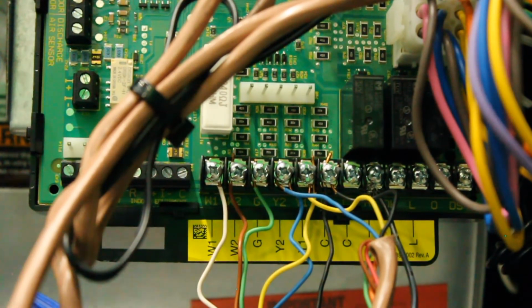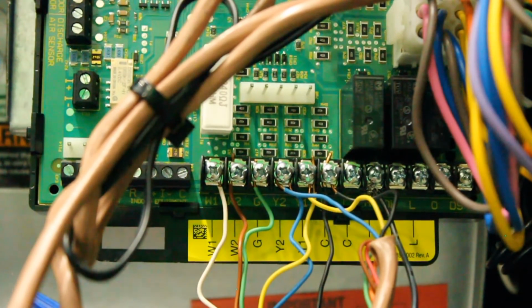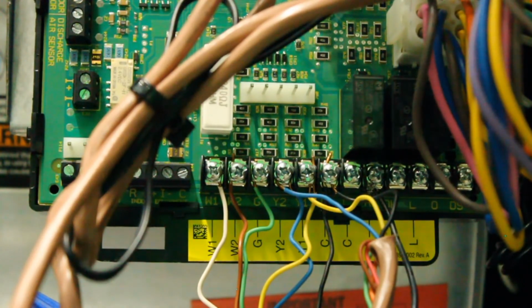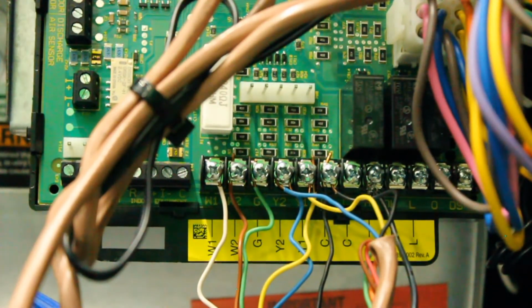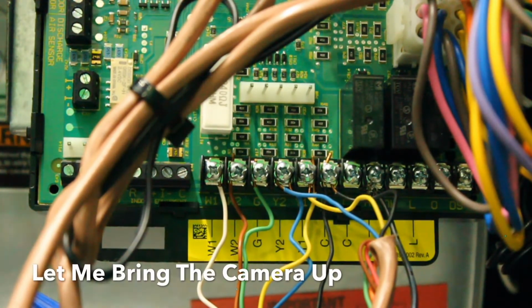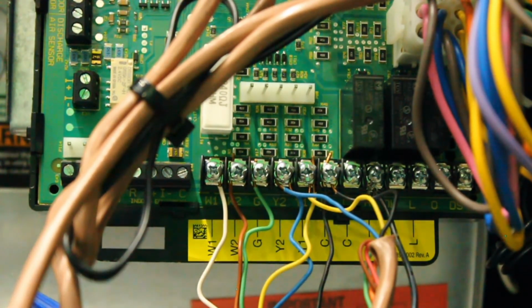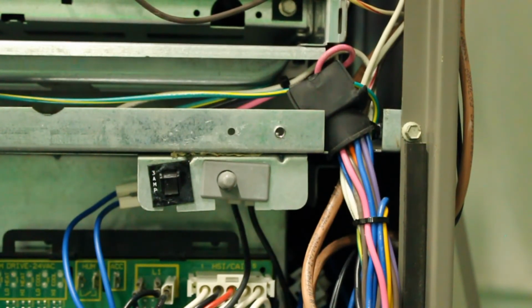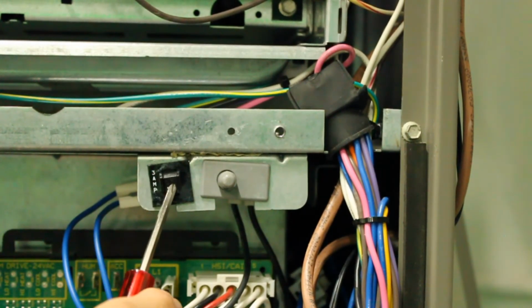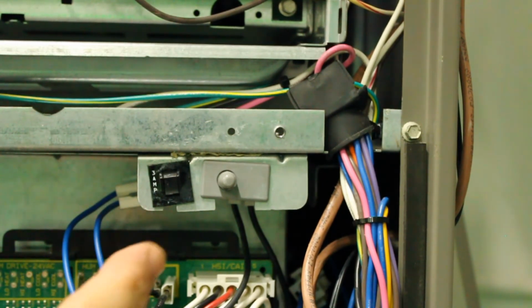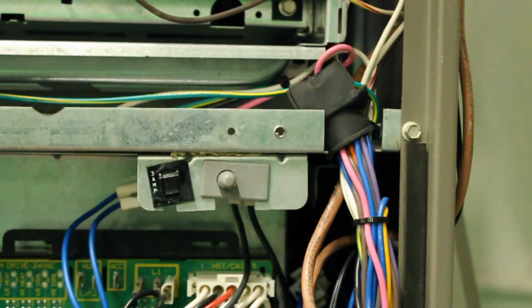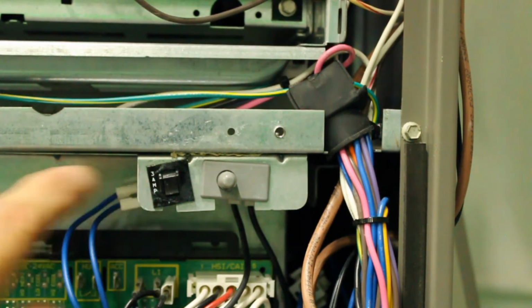But what we've done is, if it's a fuse in a board, we blew the fuse. This particular unit has a little 3 amp circuit breaker or 5 amp circuit breaker in it, which is great. This particular one, I'm going to look at it now at the top, is a 3 amp. Let me bring the camera up and take a look at this 3 amp circuit breaker. Okay, let's take a look at this here. Here's my 3 amp circuit breaker. So sometimes if we blow the circuit, the low voltage, instead of burning the board up or burning the transformer or something that's very costly, it trips the circuit breaker.